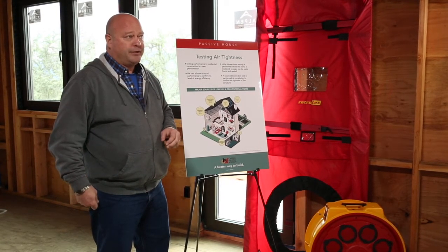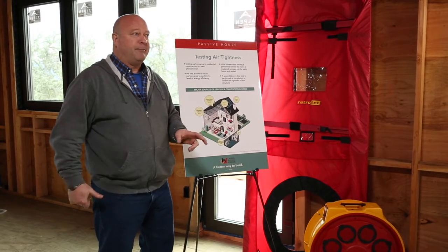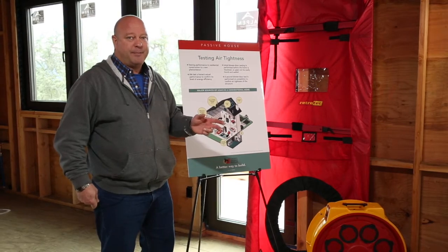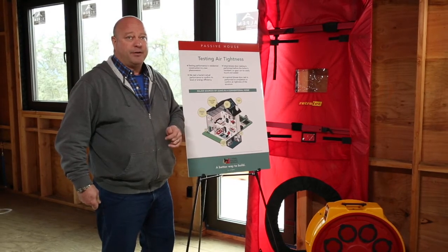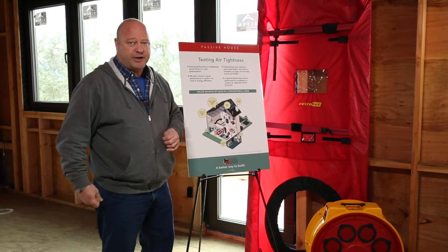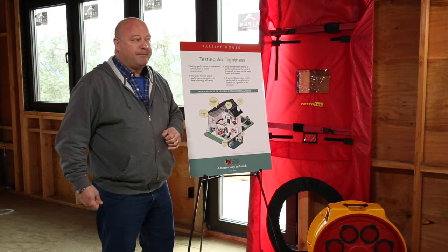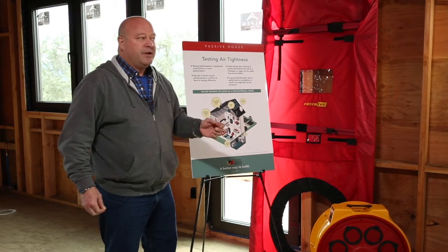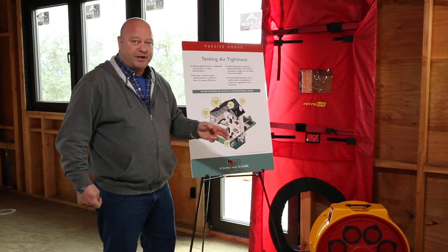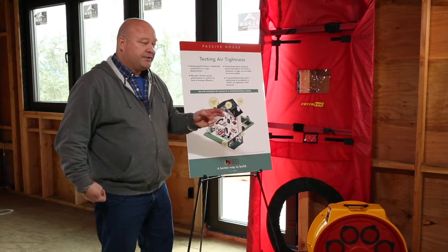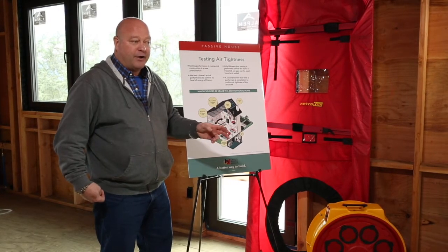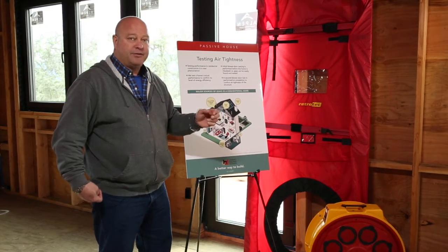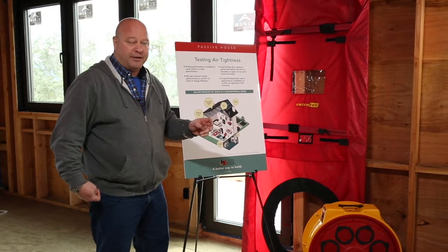A conventional building is sort of all over the map, but buildings by and large are pretty leaky because in the past, we never thought about this. We've measured buildings that were 10 or 15 air changes per hour. The state of California, the software that they use assumes 7 air changes per hour. Because air leaking out is taking with it a lot of energy, we're trying to drive it down to much less volume of air leaking.